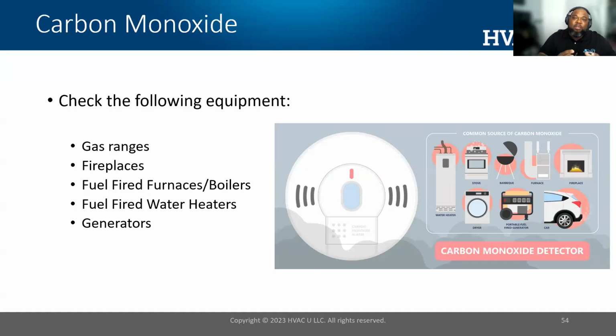However, it's not enough time for the dose to accumulate. However, we find problems when people cook for prolonged periods of time, such as Thanksgiving or Christmas, where families will congregate and they're cooking for long periods of time, and then we'll start to see those events take place. So you want to inspect those. And again, you need two things to happen. The exhaust gases need to be inside the building, and the equipment needs to be producing high levels of carbon monoxide. And remember, even low levels are not good.